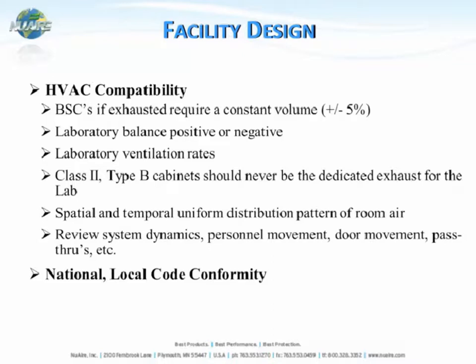When looking at HVAC compatibility, if the BSC is exhausted it requires a constant volume — you need to achieve the specified CFM and static pressure values at the cabinet itself. Review laboratory air balance — positive or negative — as well as the laboratory ventilation rate. Review the system dynamics, personnel movement, door movement, and pass-throughs. Also look at national and local codes to make sure you're following all guidelines in place.